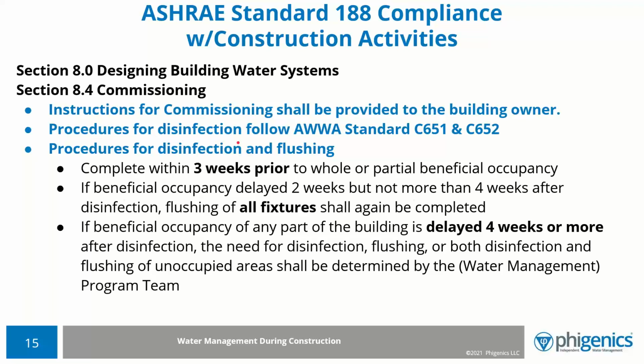It will discuss that you need to use the disinfection standards from AWWA 651 and 652. There's a paragraph that starts to discuss disinfection and flushing, mentioning that within 3 weeks prior to whole or beneficial occupancy—some of you may use the term substantial completion—you need to be disinfecting and flushing the building and preparing it so it's safe. And if there's going to be a delay in that occupancy, which is often the first business day of operations, that's not the same as receiving it from the contractor, depending on the scale of the project.